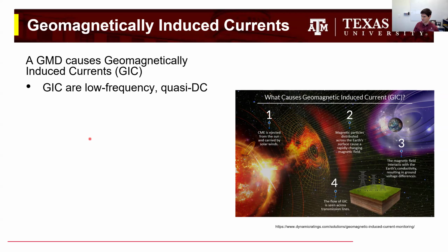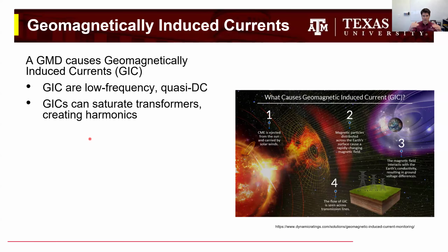So they're quasi-DC, several orders of magnitude lower than 60 hertz, and we model them in the system as DC current since compared to 60 hertz they can be viewed as DC. So when you have your normal 60 hertz sine wave on the grid - whether voltage or current, in this case current - you have your fundamental 60 hertz frequency, and when you add a DC offset to this, transformers can enter half cycle saturation.